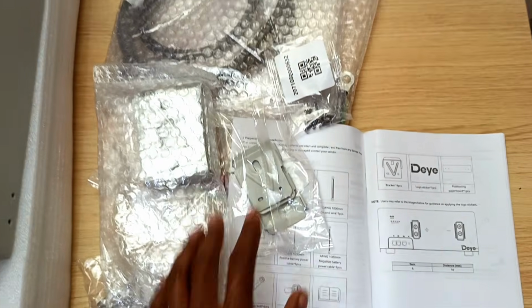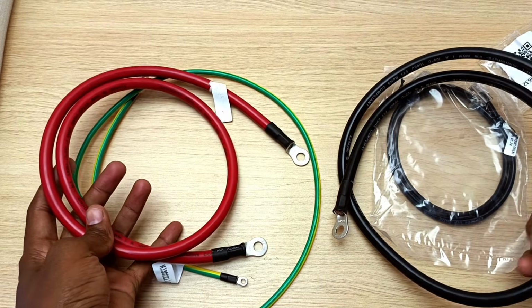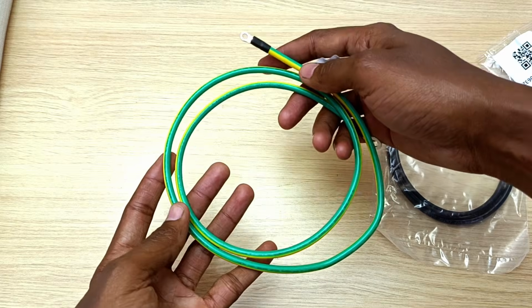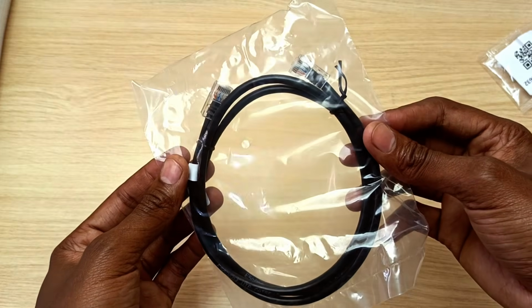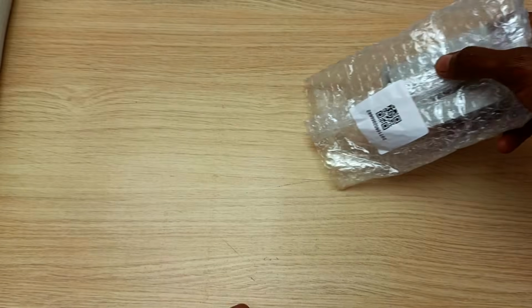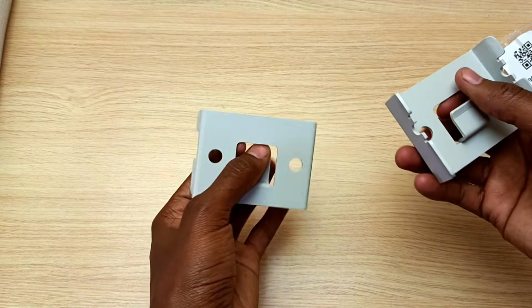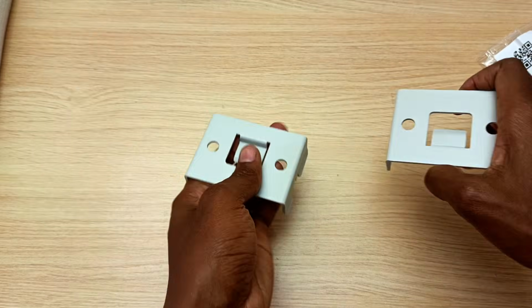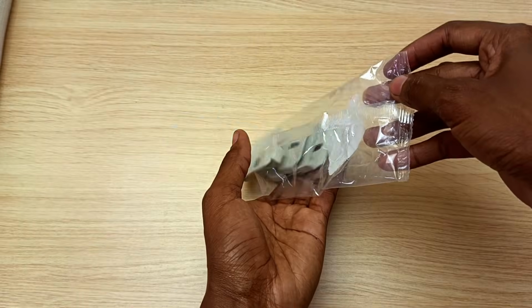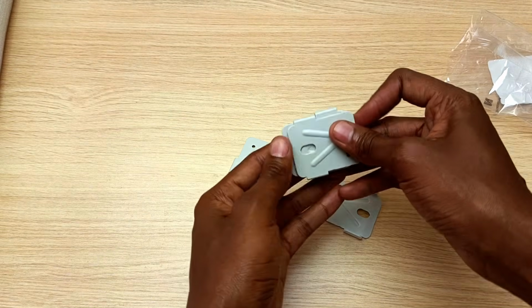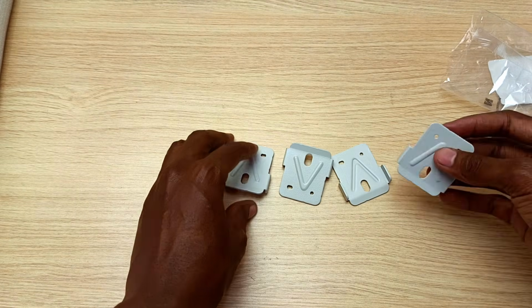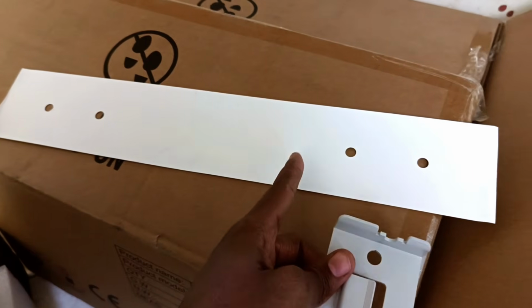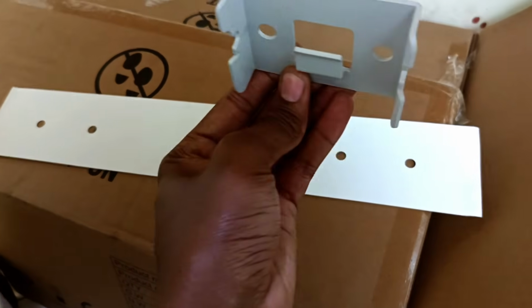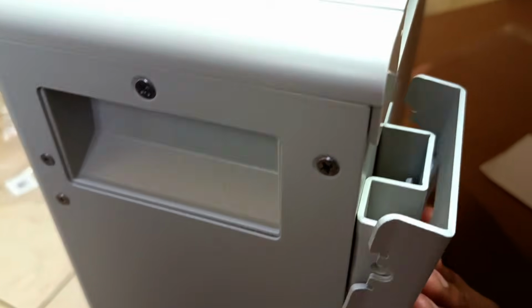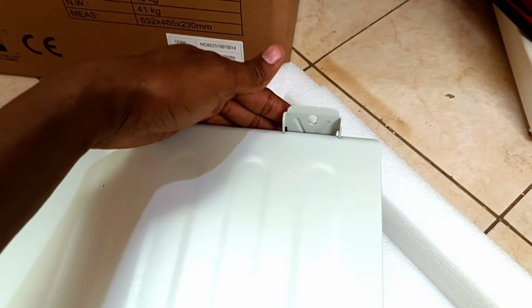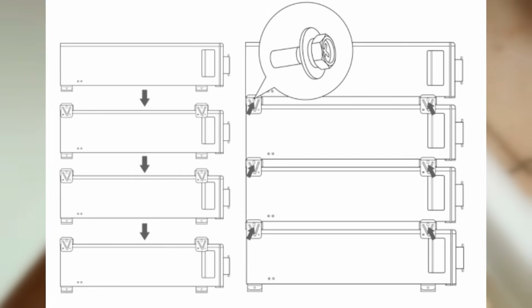Let's take a look at all the accessories that came with the battery. These are 4-gauge battery cables, 1 meter in length. Next, we have a 10-gauge protective earth cable, an Ethernet cable, also 1 meter, hooks for mounting the battery on the wall, V brackets. Now these are for connecting the batteries stacked one on top of each other. You drill the holes on the wall using this template. You mount this on the wall and then you lift and rest the battery on these brackets. With this placed, you can just place another battery just like this one on top of the other battery.